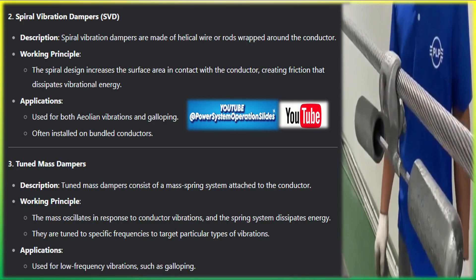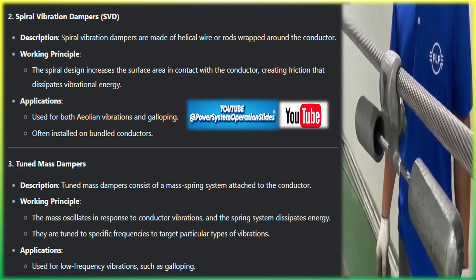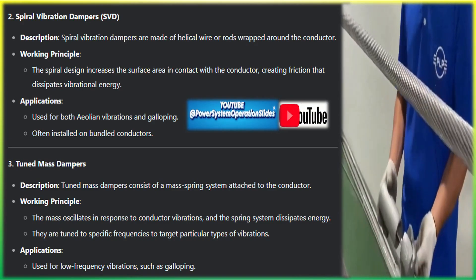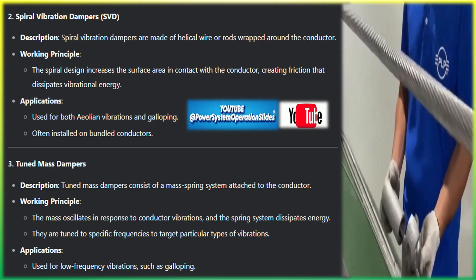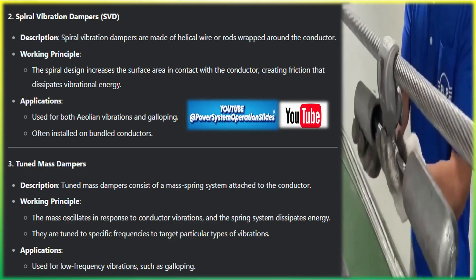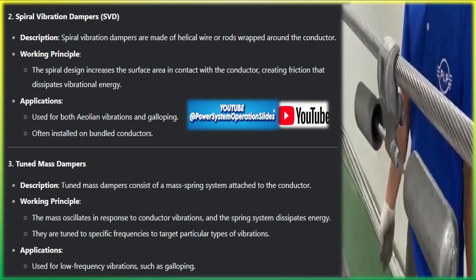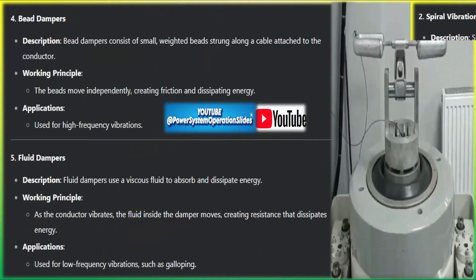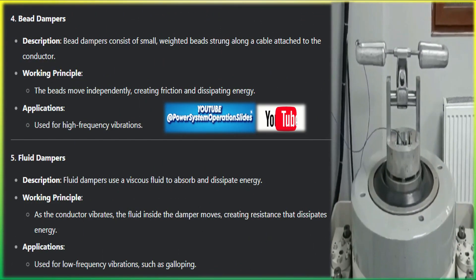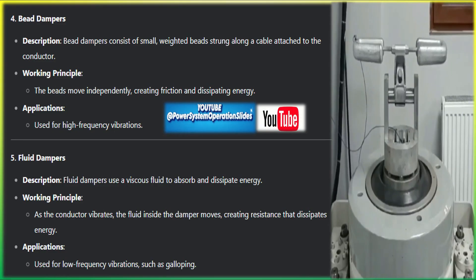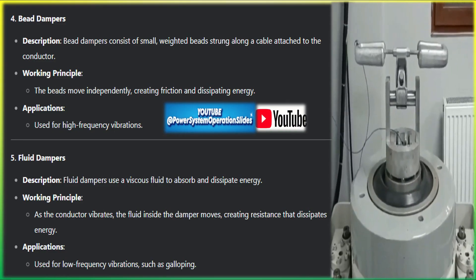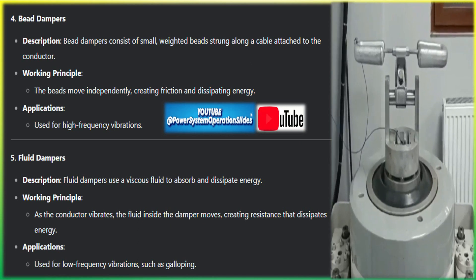Galloping is caused by ice or snow buildup on conductors, leading to aerodynamic instability. The wind flows over the ice-coated conductor, creating lift that causes large, low-frequency oscillations. Galloping results in large vertical and horizontal motions of up to several meters and low frequencies of 0.1 to 1 Hz. This can result in phase-to-phase or phase-to-ground short circuits.